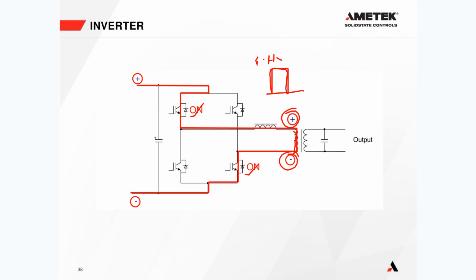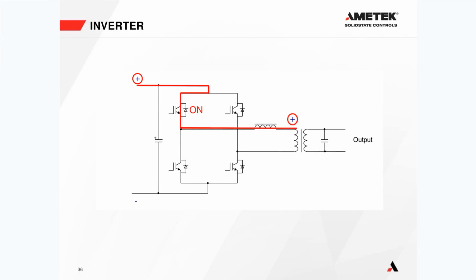But all you need to know is we have created a positive pulse, and remember, we're taking this from the battery. So if we said this was 135 volts DC, that means the size of this pulse is going to be 135 volts DC into the primary of this transformer. And then the clever thing about this inverter H-bridge, and the reason we call it an H-bridge, is because it kind of looks like an H.